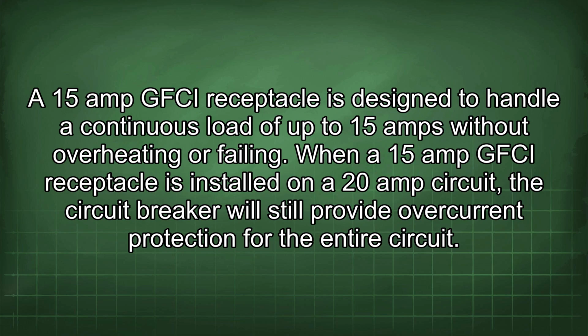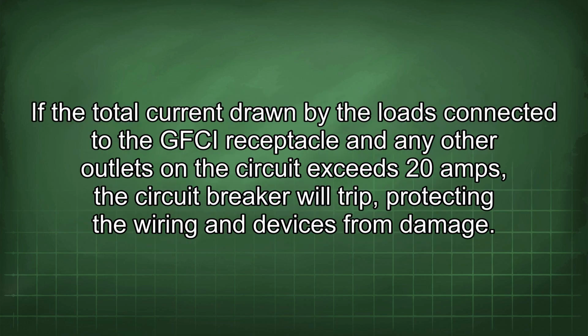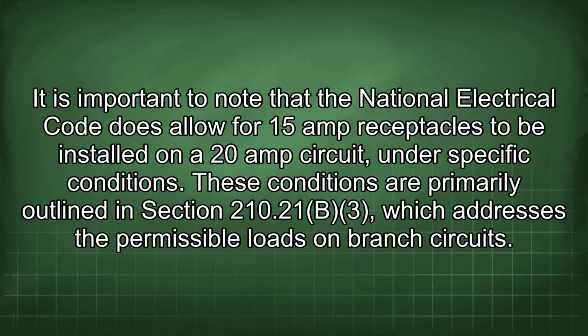When a 15-amp GFCI receptacle is installed on a 20-amp circuit, the circuit breaker will still provide overcurrent protection for the entire circuit. If the total current drawn by the loads connected to the GFCI receptacle and any other outlets in the circuit exceeds 20 amps, the circuit breaker will trip, protecting the wiring and devices from damage. It is important to note that the National Electrical Code does allow for 15-amp receptacles to be installed on a 20-amp circuit under specific conditions.